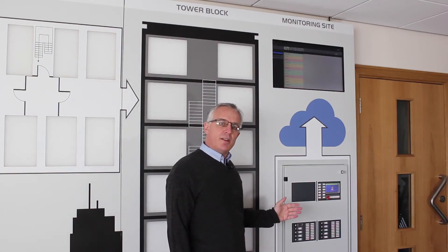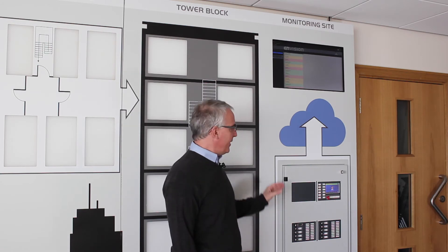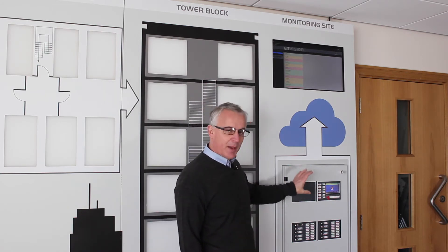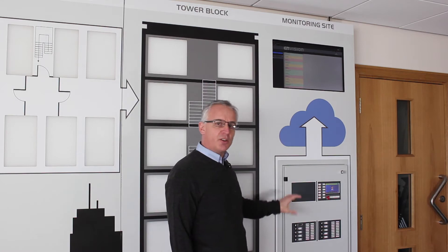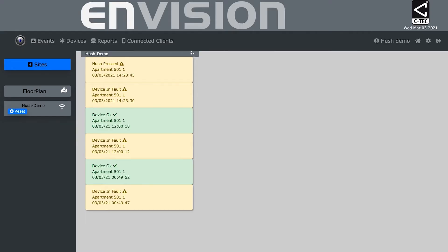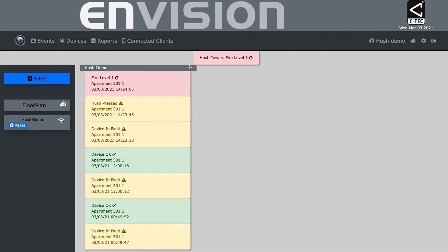Okay, as Fire Level 1 is typically and likely to be an unwanted or false alarm, it isn't reported on the ZFP's panel display, although it is logged at the panel, but it is reported off-site via the cloud-based monitoring software.